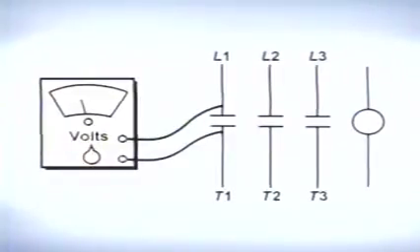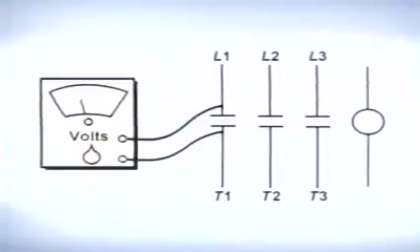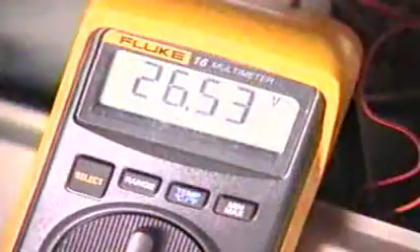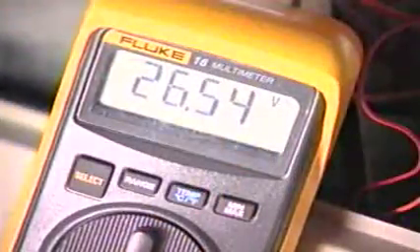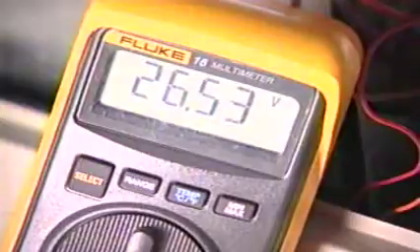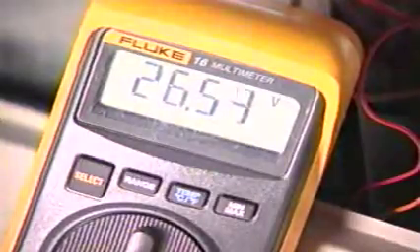The coil of the contactor should be energized and the contacts should be in the closed position. A voltage reading across the contacts that exceeds 5% of the supply voltage indicates that the contacts are pitted or bad and need to be replaced.